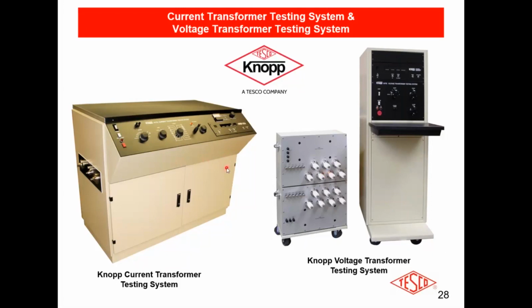But they both operate in the same fashion, the same way any kind of meter testing works as well. You have a precision transformer right here. This is on the voltage side. And you've got a loading transformer right here. Inside of this cabinet, you've got the same thing: a precision and a loading transformer. You can pair the transformer under test, which in this case on the current side is hooked up over here, and on the voltage side is connected via cables to the loading transformer.